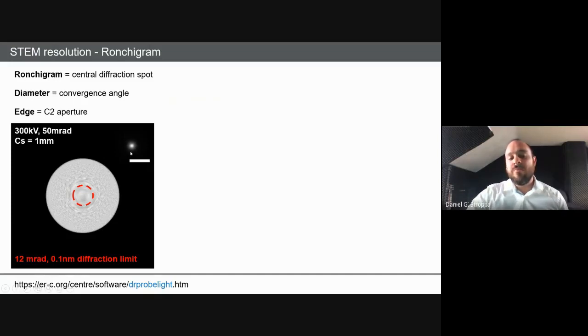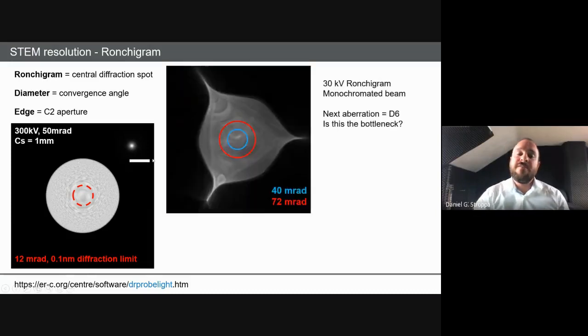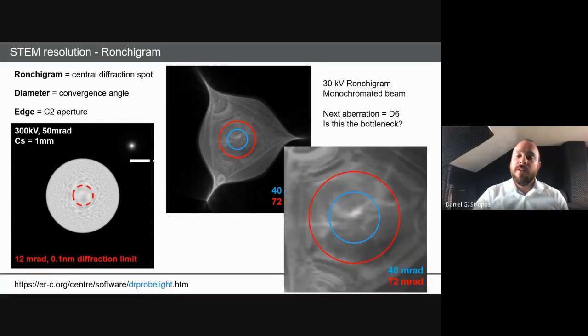So that means that the aberrations are not limiting the imaging there. To put it in a simpler way, when you're thinking about STEM, you want to make a very small probe. To make a very small probe, you need to be convergent, so you beat the diffraction limit. But as you get convergent, you have aberrations. And only with the aberration correctors do we start to get nice images coming out of STEM.